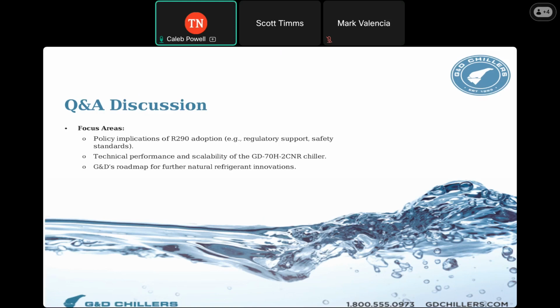I'm assuming like what you've already mentioned, not insulating, and another one is being undersized. A lot of times when people are buying on the front end, they don't think through expansion or the ability to expand. So a lot of times the chiller ends up getting overtaxed, especially during the summer, when it's already less efficient to begin with because it's hot outside. At that point you start having operational issues, which are frustrating, but also cause you to be less efficient too.